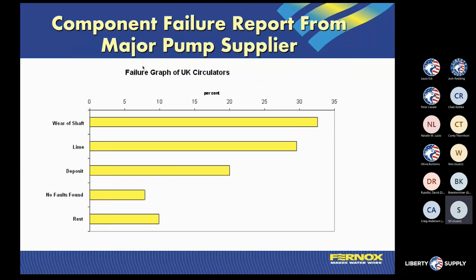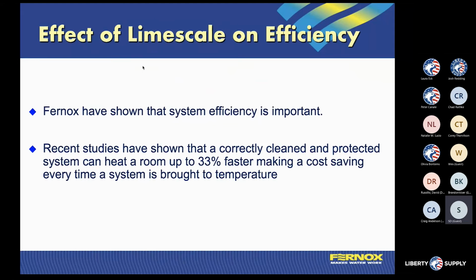What we're starting to find, even from most major manufacturers of different components, is that a lot of the warranties coming back aren't really warranties of product failure. They are warranties of deposits and limescale and things of that nature. And some are just changed with the assumption that they are failed or broken. So when we talk about efficiency, we're talking about how that effective efficiency is eroded, like we've mentioned here. That is another piece of that puzzle.